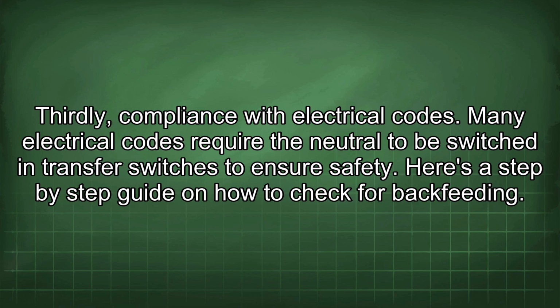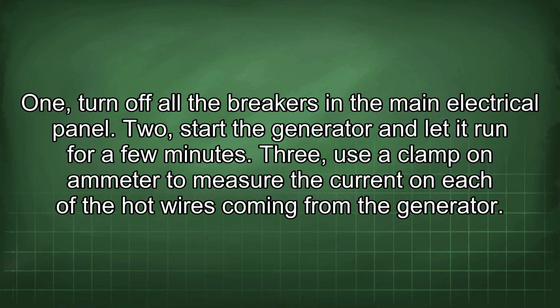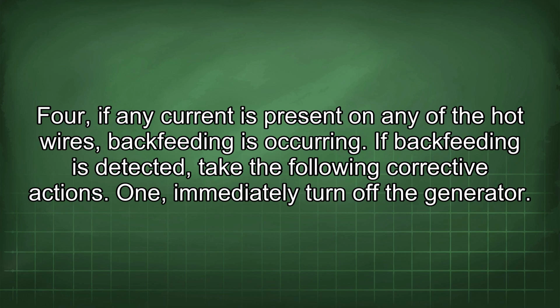Here's a step-by-step guide on how to check for backfeeding. 1. Turn off all the breakers in the main electrical panel. 2. Start the generator and let it run for a few minutes. 3. Use a clamp-on ammeter to measure the current on each of the hot wires coming from the generator. 4. If any current is present on any of the hot wires, backfeeding is occurring.